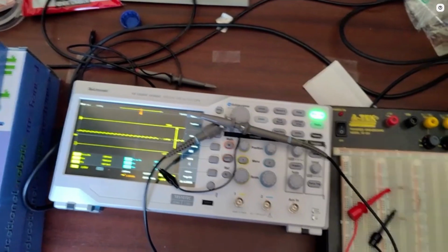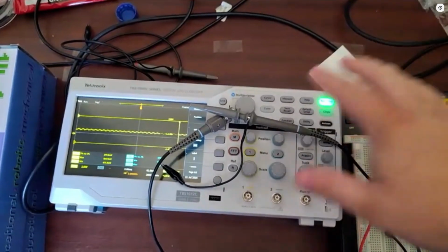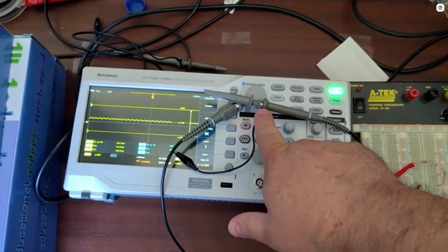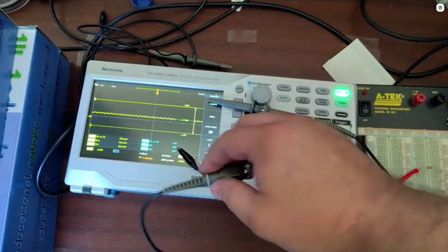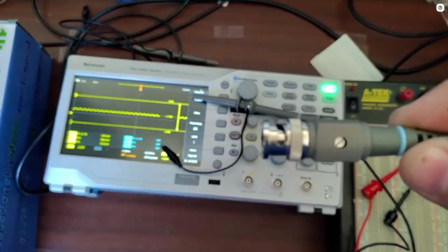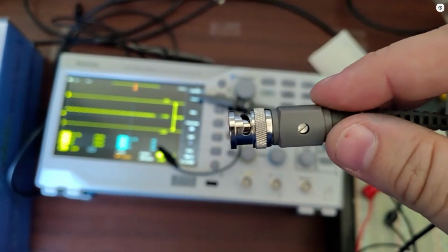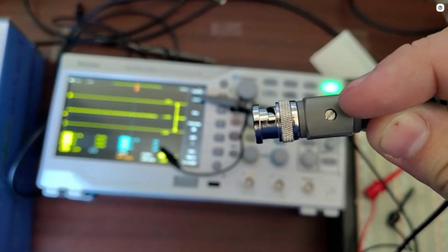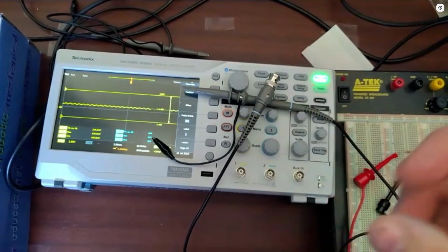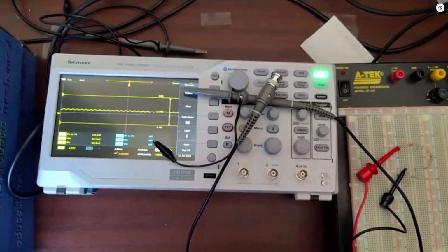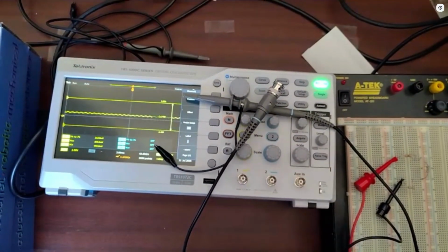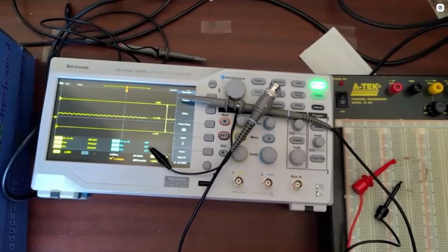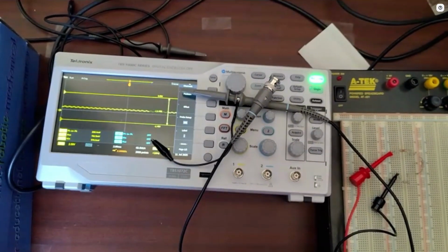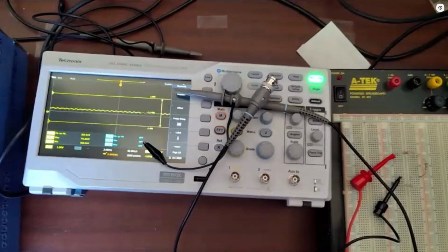What we're going to be looking at is our probe and our oscilloscope. We're going to grab one of the probes, it doesn't matter which one, and what we want to note is that on this side is our BNC connector, and as you can see right here on the end, we've got a little adjustment screw. This is what we're going to use to calibrate the probe to the scope. The reason we do that is each of these probes is different, so we have to calibrate the probe to the oscilloscope we're using. Because of those minute changes, we can get some issues that crop up while we're doing this.